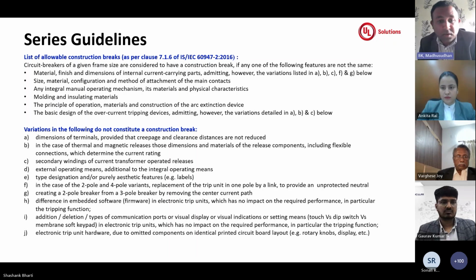And also your overcurrent tripping devices and the magnetic tripping devices, the construction should be the same. If within the range you are bifurcating, or any changes in the design on this part, it will be treated as an additional construction, and you need to clearly bifurcate these changes and have the constructions, samples, or ranges separately done for the testing and the other requirements. Yeah, next slide, please.